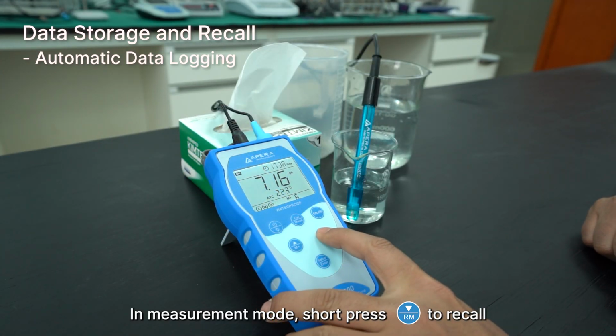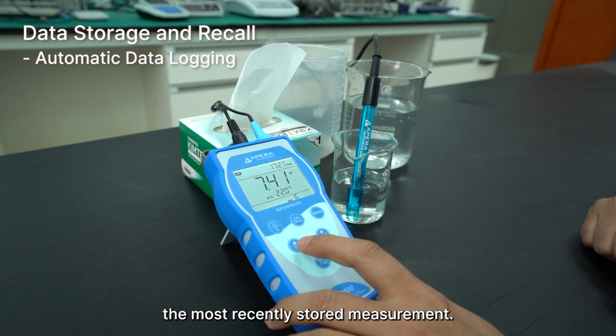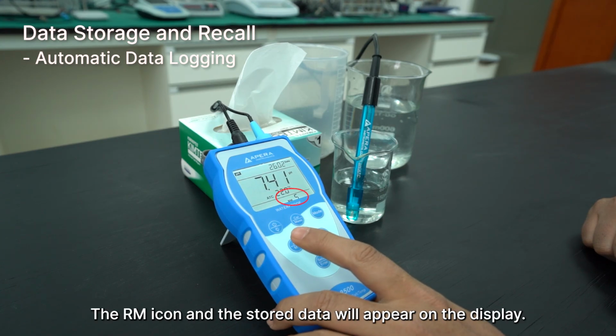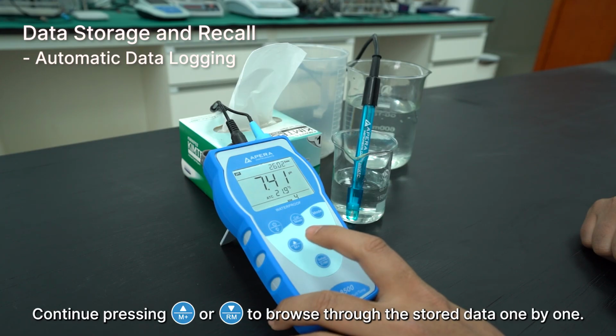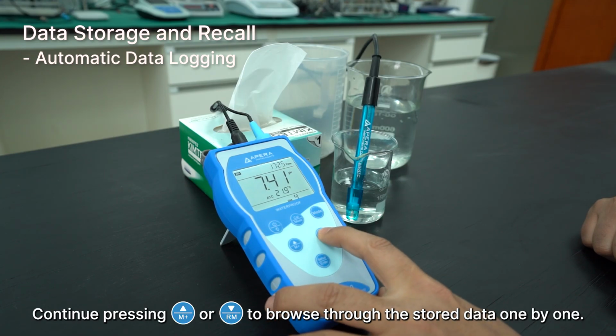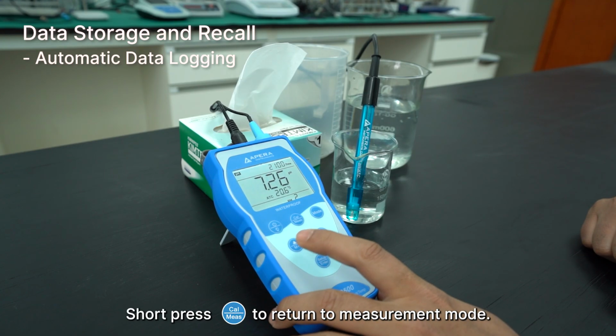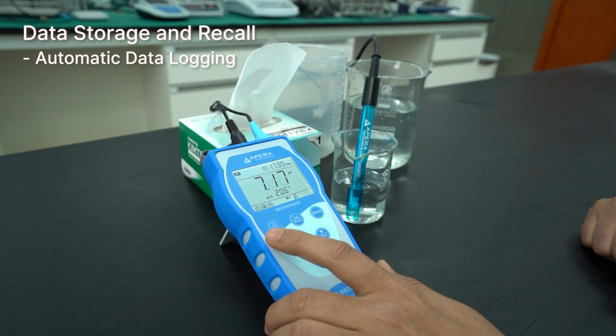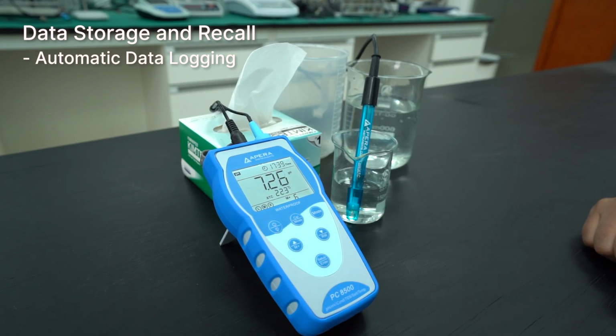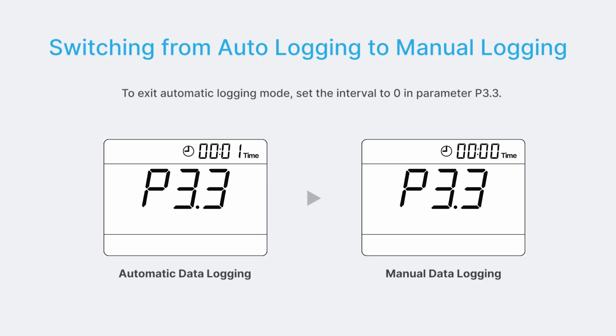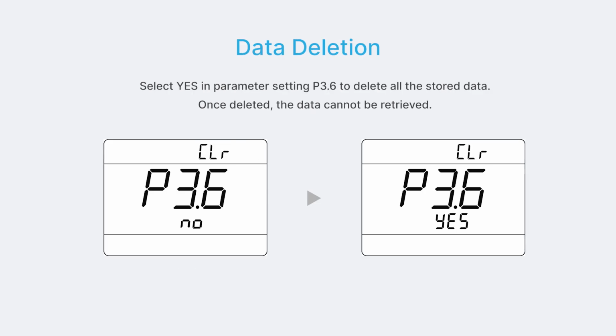In measurement mode, short press RM to recall the most recently stored measurement. The RM icon and the stored data will appear on the display. Continue pressing up or down to browse through the stored data one by one. Short press Measure button to return to measurement mode. To exit automatic logging mode, set the interval to 0 in parameter P3.3. Select Yes in parameter setting P3.6 to delete all the stored data. Once deleted, the data cannot be retrieved.